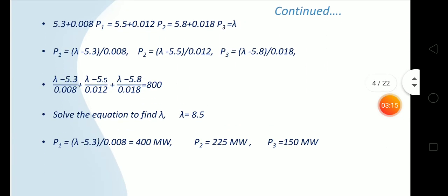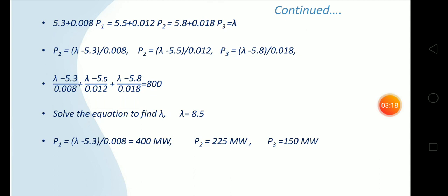We can write the incremental fuel costs as equal and equal to lambda. So P1, P2, and P3 can be written in terms of lambda as: P1 = (lambda - 5.3)/0.008, P2 = (lambda - 5.5)/0.012, P3 = (lambda - 5.8)/0.018. Substituting into P1 + P2 + P3 = 800 and solving, we get lambda = 8.5. Then we substitute this value of lambda into the equations for P1, P2, and P3.